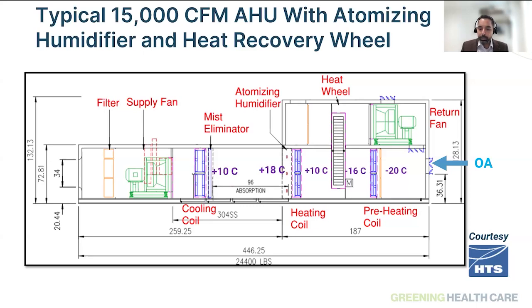So when you're considering this, there are obvious questions that we get asked. What happens to my existing unit? Do we have the space in the mechanical room to fit this unit? Or could this be a standalone system? There are multiple configurations that are possible with these systems these days. So we would highly recommend you work out all those options when you're planning for replacement of these units. Like for like is going to push you 10, 25 years behind in terms of meeting your sustainability goals. So consider all the options on the table that you can use now, given that the CSA now allows us to consider adiabatic humidification as one of the means to replace these systems. So it is recommended to look at these options.